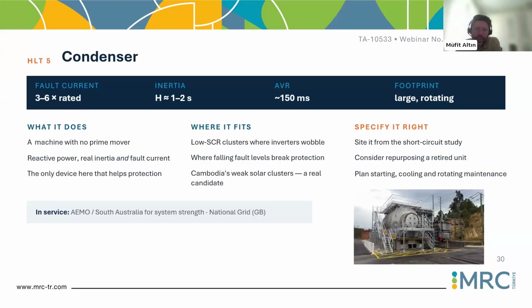Synchronous condensers, you can think of as a synchronous machine with no prime mover. Just for the internal losses it is consuming active power, and the reactive power and the inertia come with the fault current, of course, supplied directly from the rotating mass of the machine. So this is a bit interesting: as I said, if you have old technology or decommissioned power plants, you can use them, if it fits in your system, to support and also increase the renewable generation capacity and also, of course, stable operating conditions. I think you need to start again with load flow and short circuit studies, and RMS studies for this. Maybe later also an EMT study if there are other IBRs, converters around, and you can look at the general view and see what is going on.